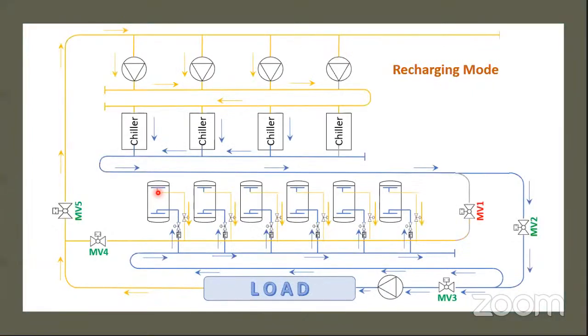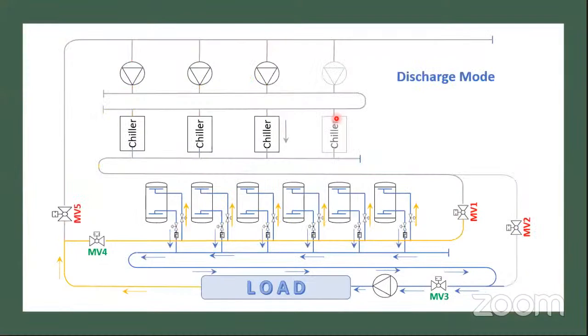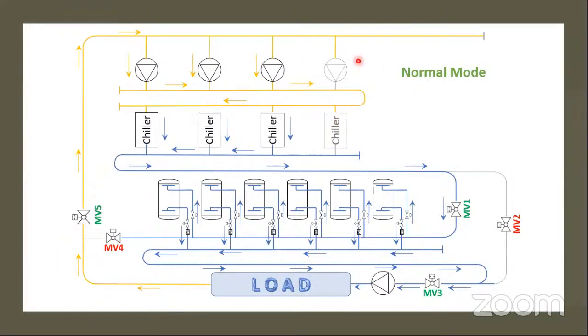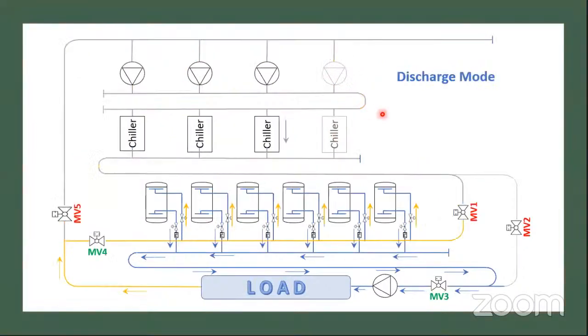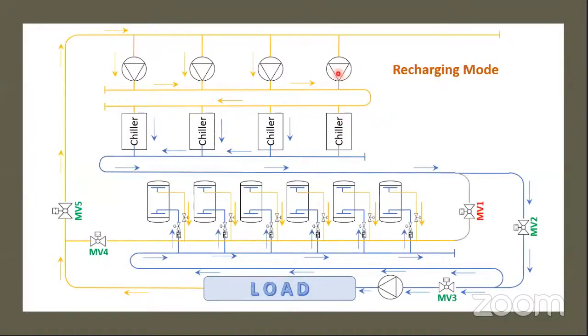When the power is back, then comes into the picture the recharging mode. The tanks discharged in the previous mode, and how the recharging mode would happen is that the chiller will supply to the load as well. You see, the secondary pump is drawing chill water from here, and you see this extra chiller has come into operation. This chiller was off. This is our standby chiller, but in recharging mode, this extra chiller has also come into operation for a reason: these three chillers will be busy catering to the load, and some surplus flow is required for the charging of the thermal storage tank. That surplus flow will pass from here.